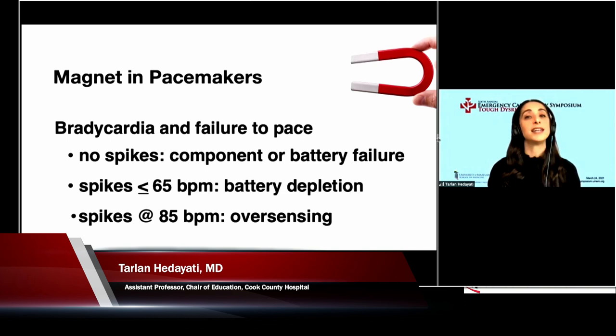It's great that you've got the pacemaker back online. That patient is going to need that pacemaker switched out. If you put the magnet on and the pacemaker fires up and the spikes are at a relatively normal rate, say 85 beats per minute, then you know that something interfered with that pacemaker, most likely oversensing, and that's what caused your failure to pace. So that's great, you've got the pacemaker back online. Well done, another life saved.